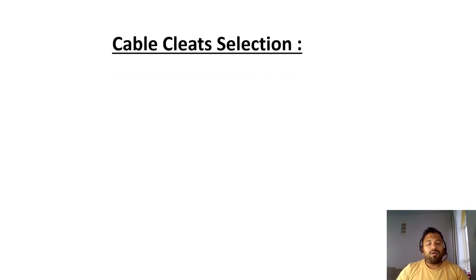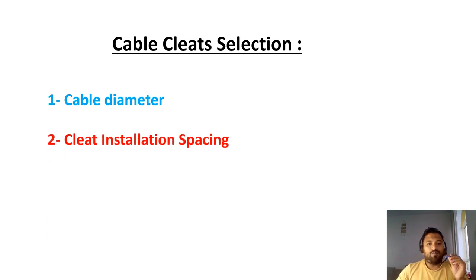Now we will see the cable cleat selection process. What are the things required while selecting cable cleats? First one we require cable diameter. So consider this is a cable. It has a diameter. So what is the diameter of that cable? Second thing is that cable cleat spacing installation. Between the cable you are installing between these two points, what is the spacing distance between the cleats?